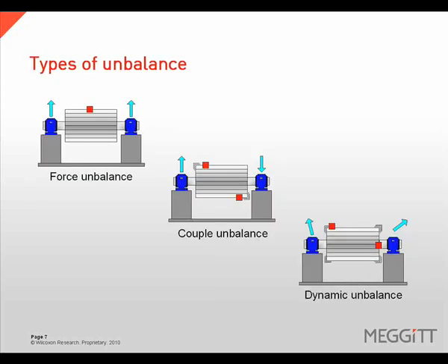There are three types of unbalance: force unbalance, couple unbalance, and dynamic unbalance. All three types exhibit vibration at 1 times rotational speed. To distinguish between them, we need to use phase readings.